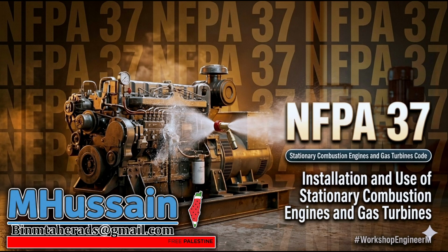But what about the trapped valve? They couldn't move the valve on the engine, so they went upstream. They intercepted the fuel supply line before it reached the enclosure and installed a remote manual shutoff. So a responder can cut the fuel from a safe distance. But they added redundancy. They also installed a solenoid-controlled automatic valve tied directly to the building's fire alarm. Oh, that's brilliant. So if the heat detectors trip, the alarm fires, the solenoid drops closed instantly.